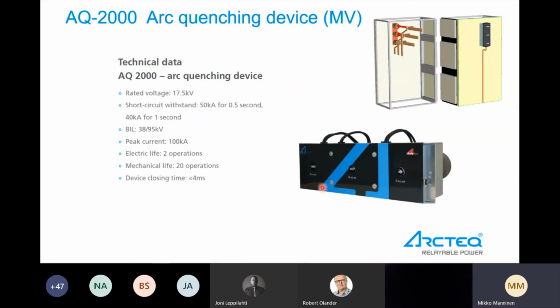The idea is very similar to the low voltage ones. It is 17.5 kilovolts, short circuit 50 kiloamps for half a second, electric life 2 operations and mechanical life 20 operations. For this unit, one good tip is that there are some micro switches inside, and this device doesn't start charging before the micro switches are properly pulled out.